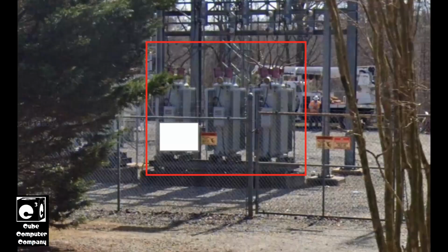So you're wondering what caused the outage. When the power came back on, we were getting 130 volts, which led me to believe it was possibly a failed voltage regulator at the substation. The substation feeding this area has regulators on every three-phase circuit out of it, and this sub has about 7 circuits. The regulators are beyond the reclosers, so when the regulator shorted, it tripped the recloser to lockout, which explains why we lost power.